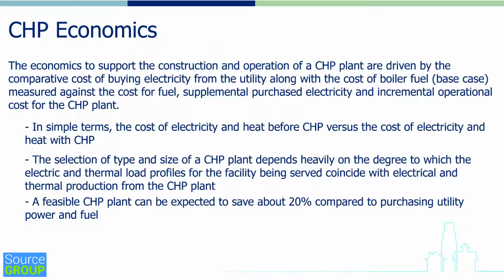The selection of type and size of CHP plant depends heavily on the degree to which the electric and thermal load profiles coincide with the facility's loads being served. This means that as you generate electricity at a particular level, it will also generate a certain amount of heat with that level. Those levels need to match the loads as closely as possible to what the requirement of the facility is. And lastly, a feasible CHP plant can be expected to save about 15 to 20% compared to purchasing utility power and fuel. That equates to somewhere between 5 and 7 year straight line payback.